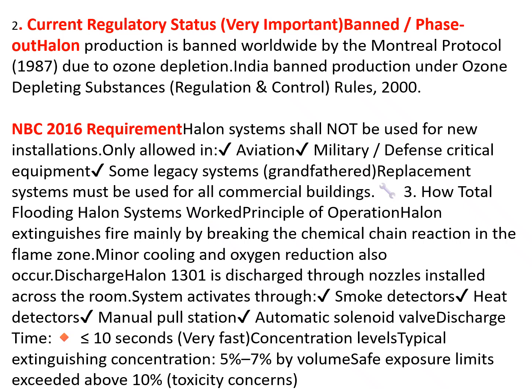Dear friends, I have in the previous slide description told you that halon systems are no more recommended. We'll discuss the current regulatory status. They are phased out. Halon production is banned worldwide by the Montreal Protocol 1987 due to ozone depletion.